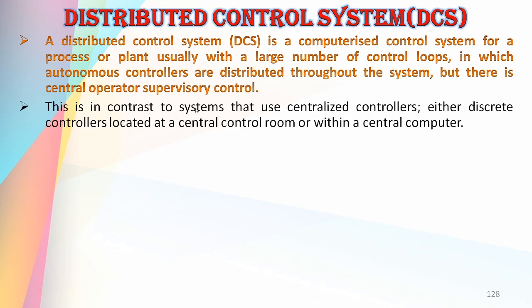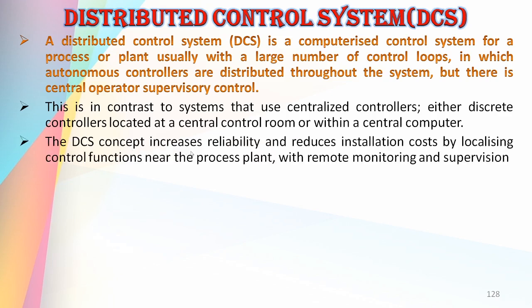This is in contrast to systems that use centralized controllers — that is what SCADA uses — either discrete controllers located at a central control room or within a central computer. The DCS concept increases reliability and reduces installation cost by localizing control functions near the process plant with remote monitoring and supervision.